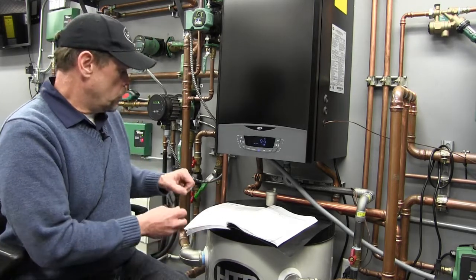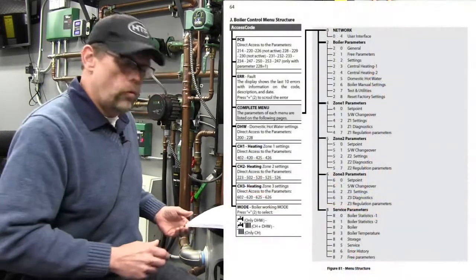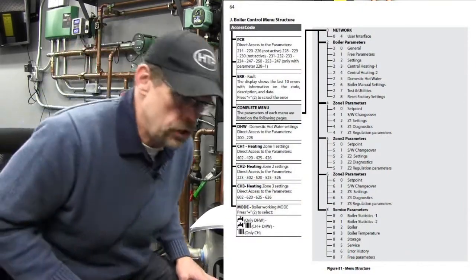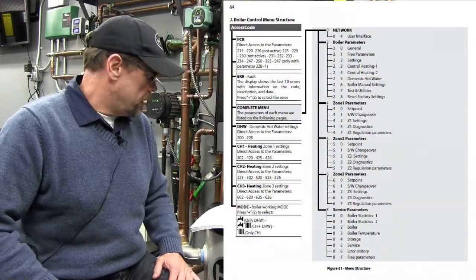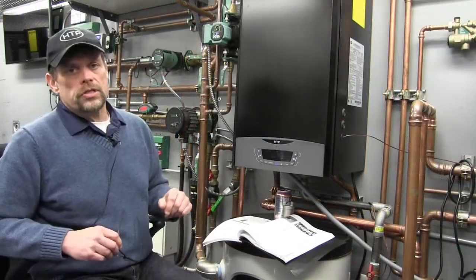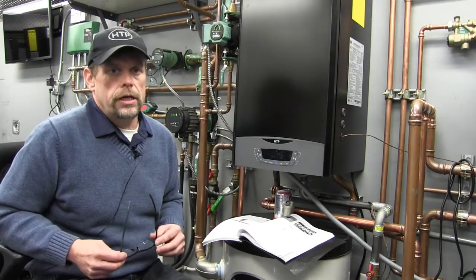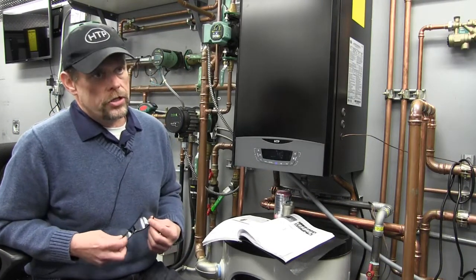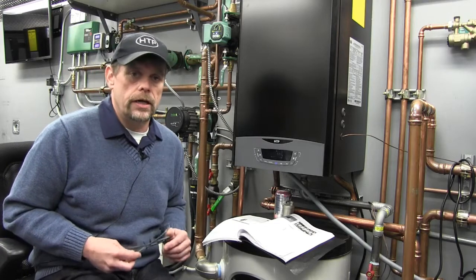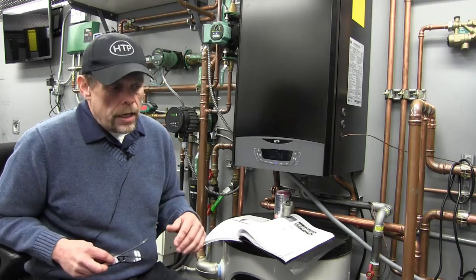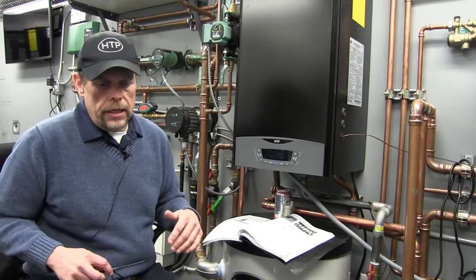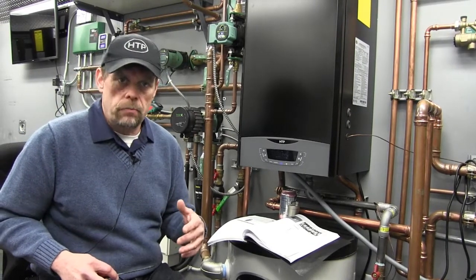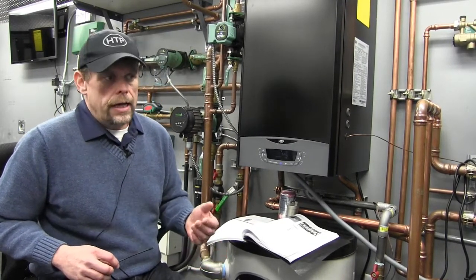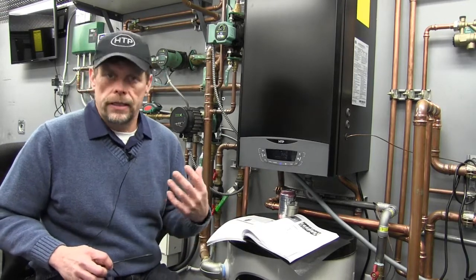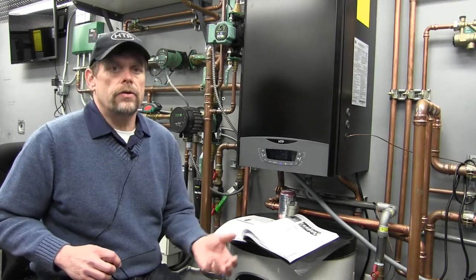So at this point, we're going to dig into the install manual. If you'd be kind enough in the install manual to turn to page 64, we'll begin to dig into this control menu. When we were discussing the temperatures on the central heat, we were discussing set point operation. And I think just for clarification, set point is not a limit. Set point is an operating parameter. The boiler has a built-in limit. The limit is 190 degrees.